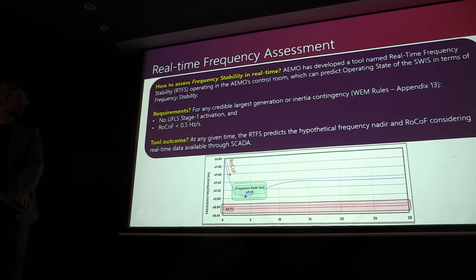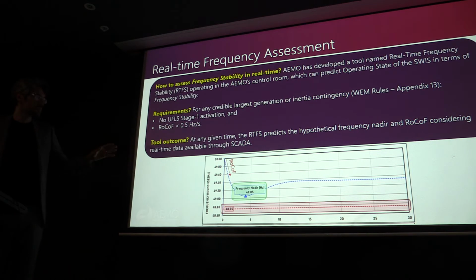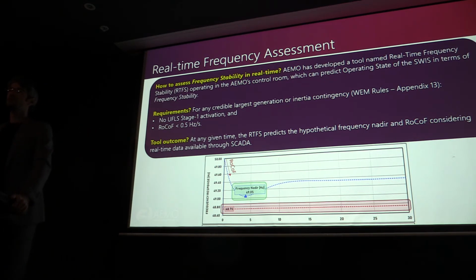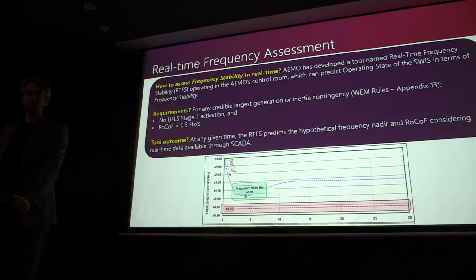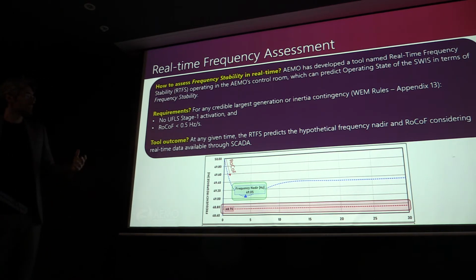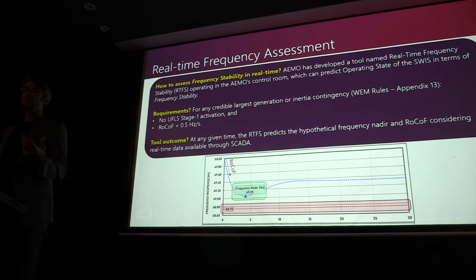So the tool outcome is exactly like this, but this is a hypothetical trip. What the tool does is recognise the largest unit of the system, and ask what would happen to the frequency if we were to lose that unit. If we see any response that is not within the requirements, we take remedial actions. For example, one is to provision more spinning reserve. We've got other remedial actions as well, but I don't want to delve into them. This is just a quick background on the tool. The inputs of the tool are SCADA data, the real-time data available through SCADA.